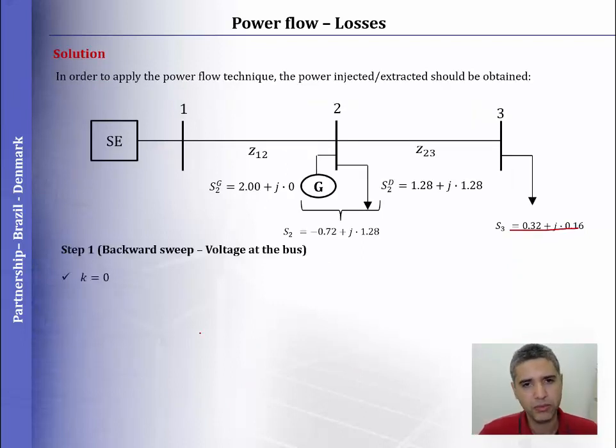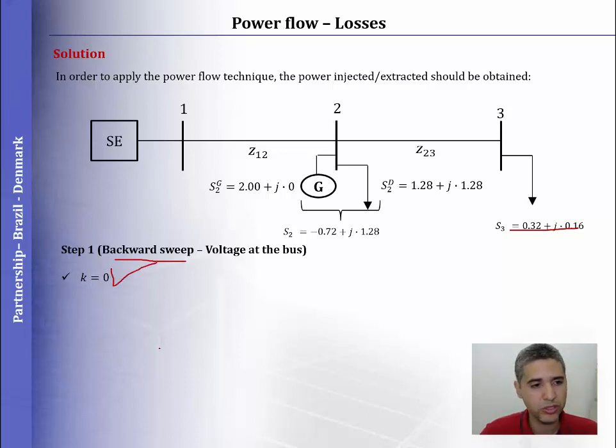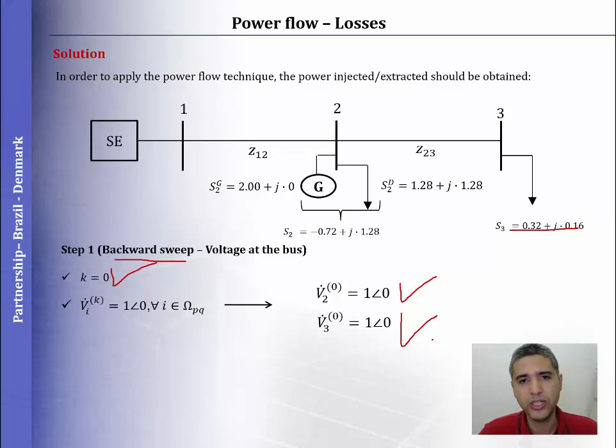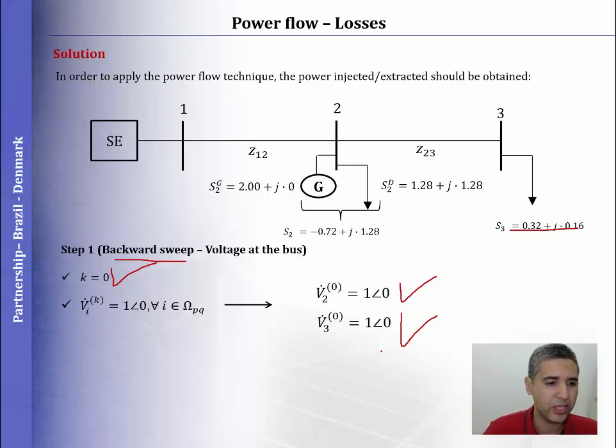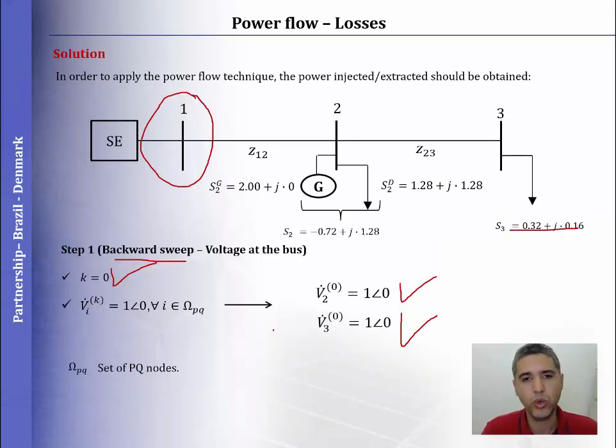Starting the backward-forward method, we begin with the backward sweep, which means going from the last bus to the first bus. The counter should be equal to 0 at the first iteration. We initiate the voltage at bus 2 and bus 3 equal to 1, because the voltage at the substation is 1. One common rule is to use the same value of the voltage at the substation.